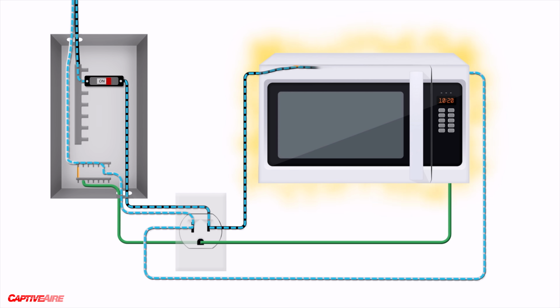But like in this case, if a cable was shorted to the appliance, instead of just leaving the frame at 120 volts of potential, which could be deadly, the current would take the path of least resistance through the ground wire and flow around the load. Since the resistance through this ground wire would be so low, the current would be very high, but only momentarily, as that high current would trip the circuit breaker and stop all current flow.